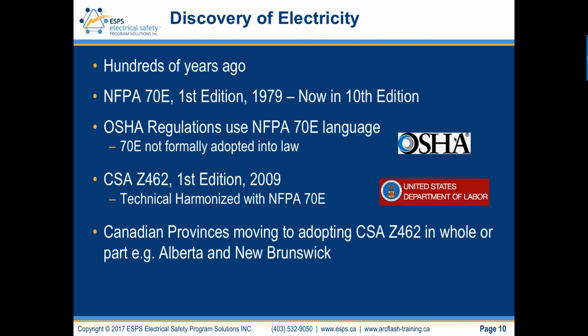So again, NFPA 70E came along and OSHA said to NFPA, you've got this safe installation standard. Can we have something about safe work practices? And that document evolved. It had too much safe installation content in it. And I'd say the 2004 edition is where it really got cleaned up. And that's where arc flash also became more prominent in it with the hazard risk category table method. As far as Canada, we didn't have a Canadian document until 2009.